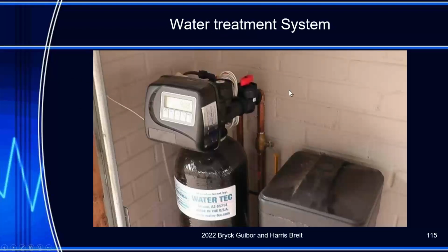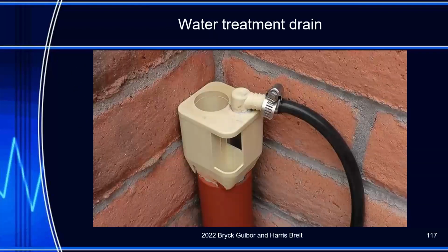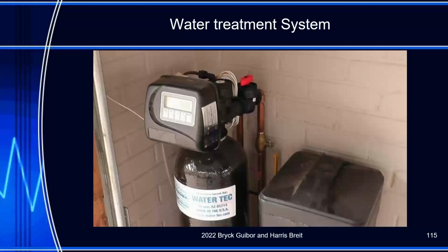Does anybody here inspect water softeners, or you just say we don't inspect them, take a picture and move on? Move on. I actually look at water softeners. Most are dry brine. If you look in the brine tank and there's water, especially above the salt, that's usually an indication of a problem. I don't get too in depth, but I look for a few basic things like that. I don't look at anything. In water treatment, I know these people; they're nice, but I don't get involved. I say I don't inspect them. You need to get this inspected, and then I'm gone.